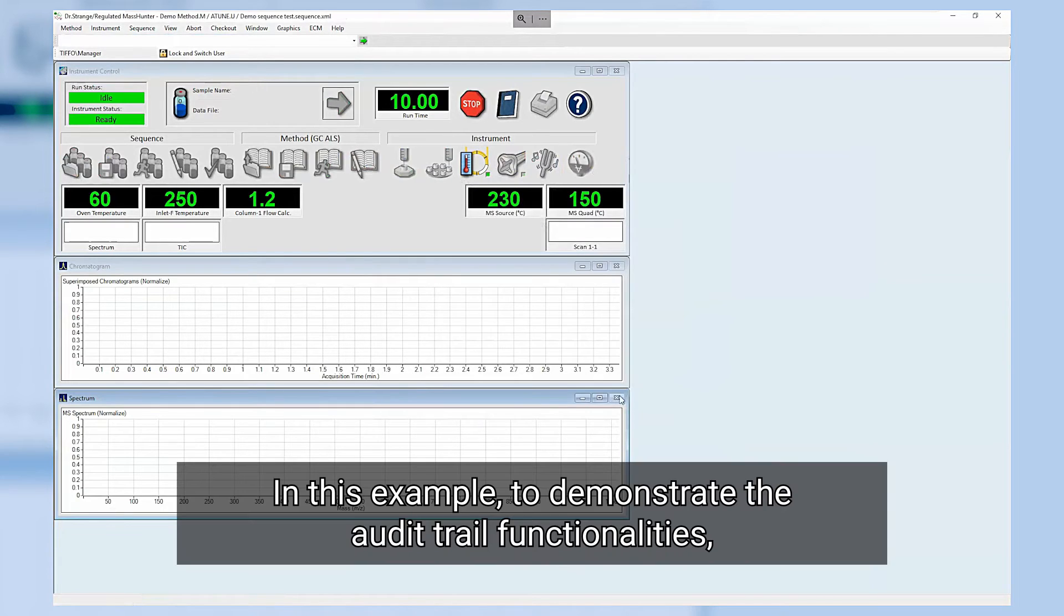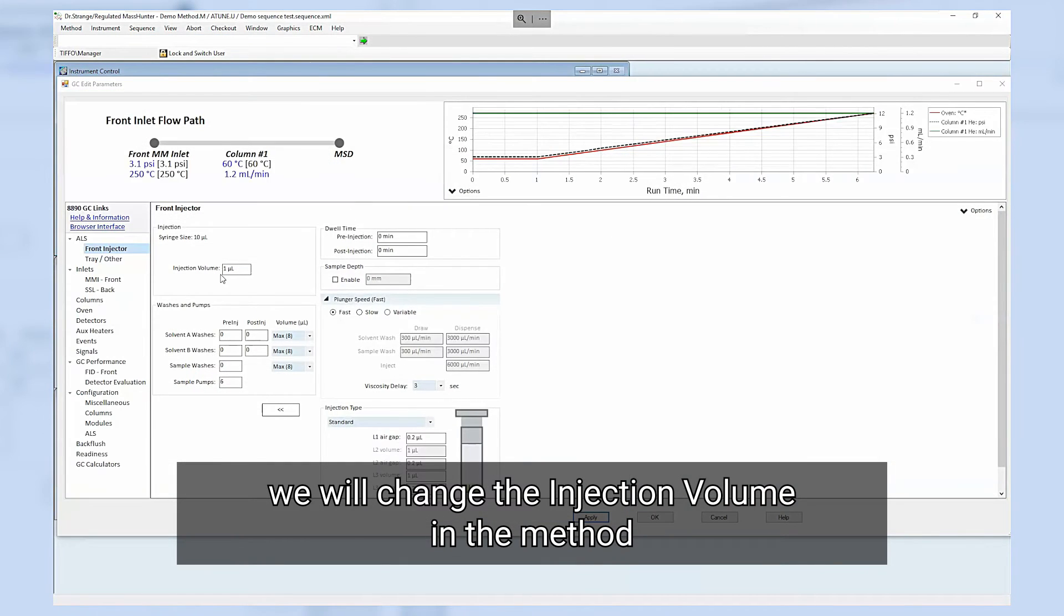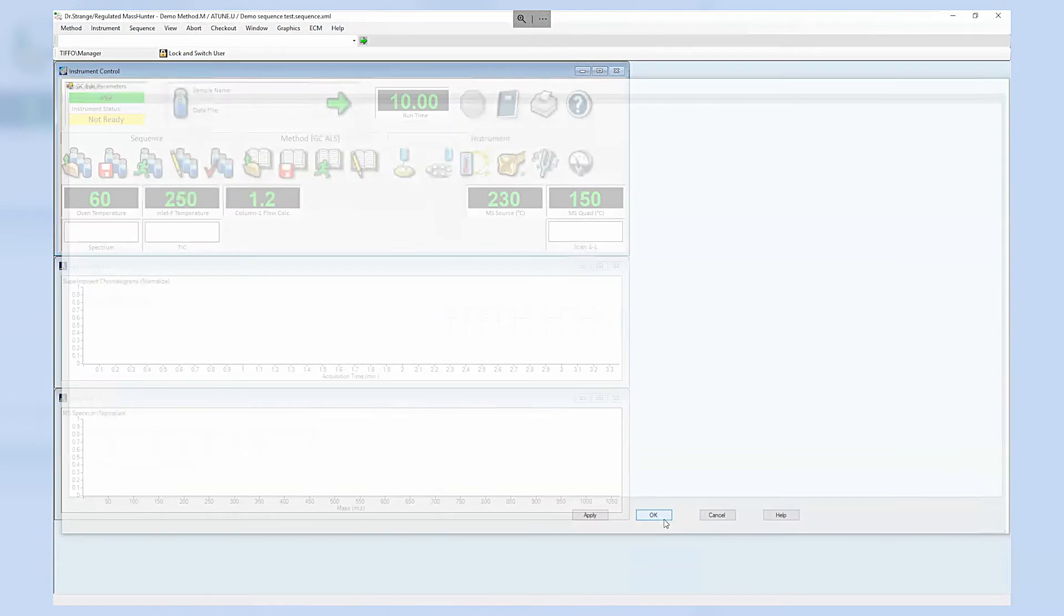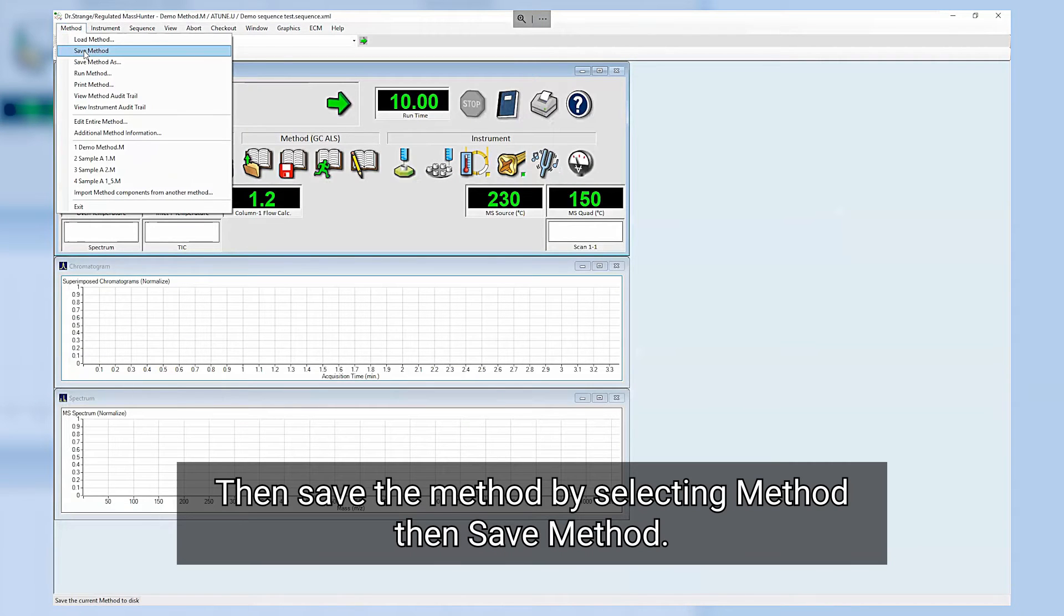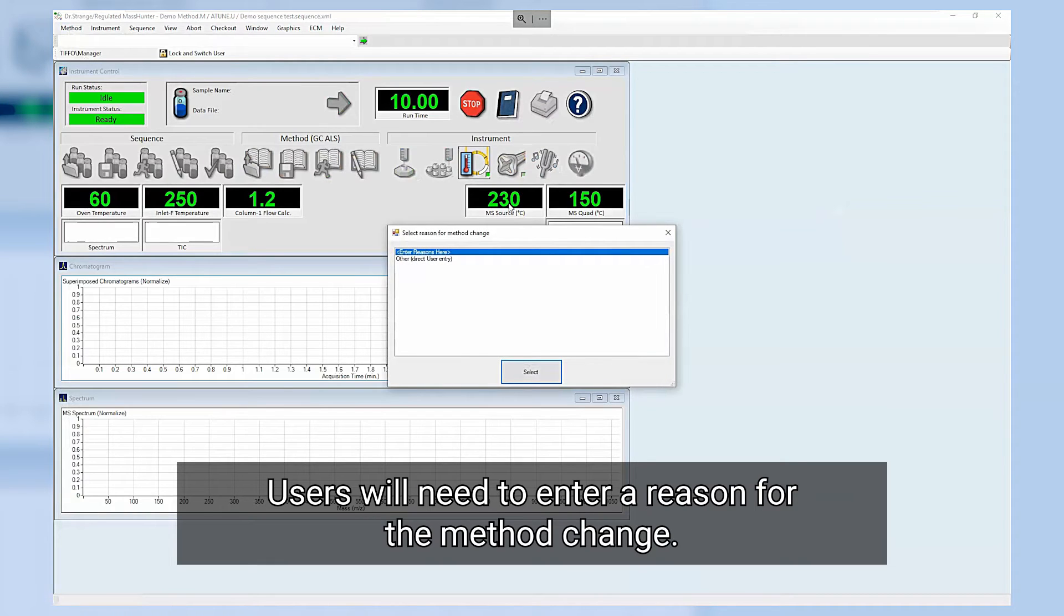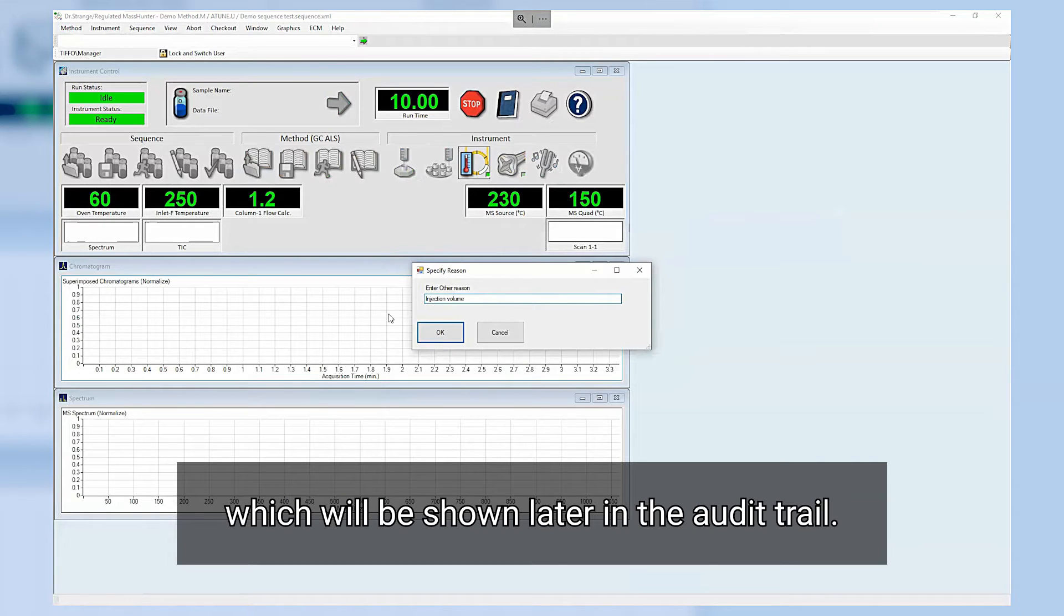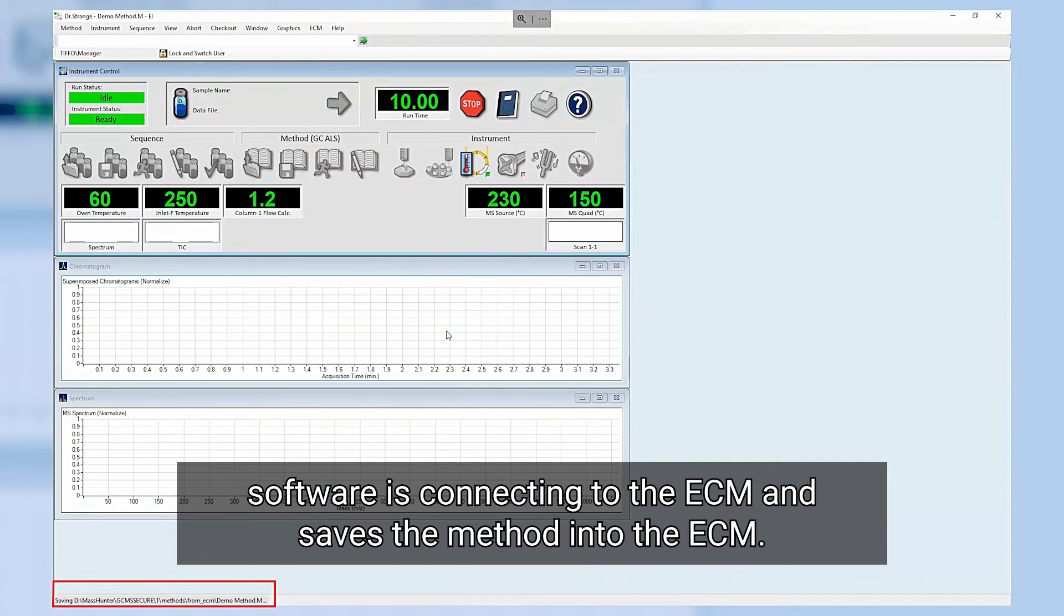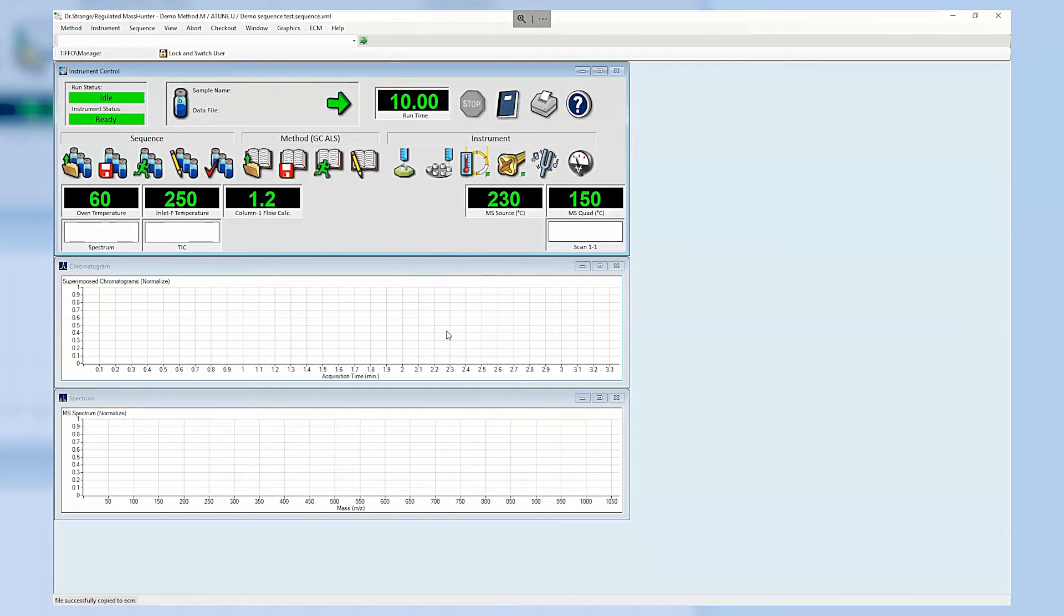In this example to demonstrate the audit trail functionalities we will change the injection volume in the method from one microliter to two microliters. Once that is done click OK. Then save the method by selecting Method then Save Method. Users will need to enter a reason for the method change. As a reason we will enter injection volume which will be shown later in the audit trail. The bottom left corner of the screen shows that the software is connecting to the ECM and saves the method into the ECM.